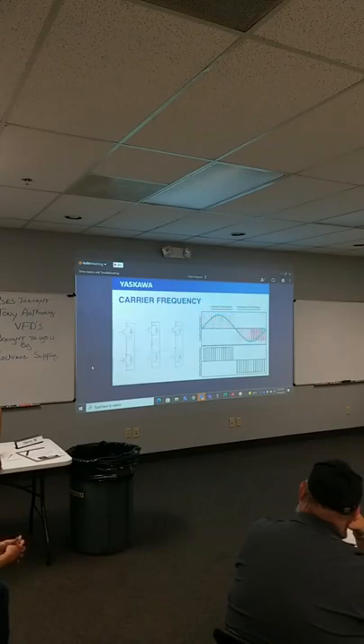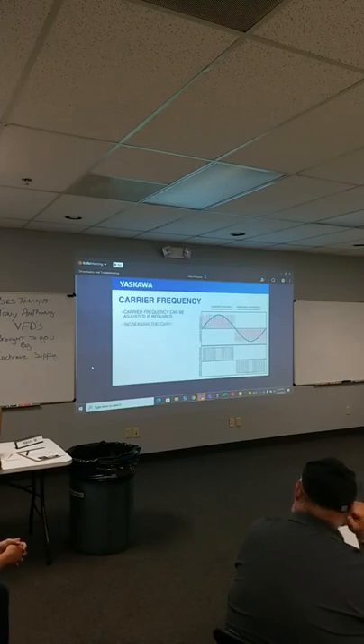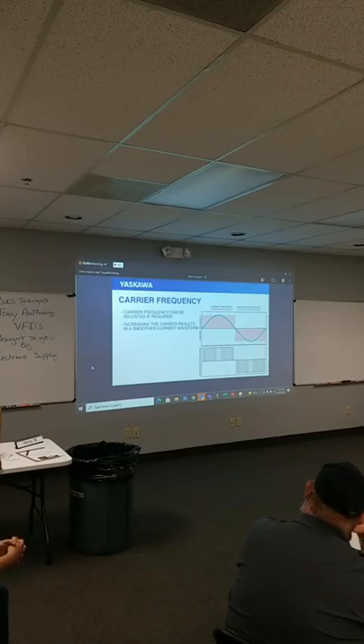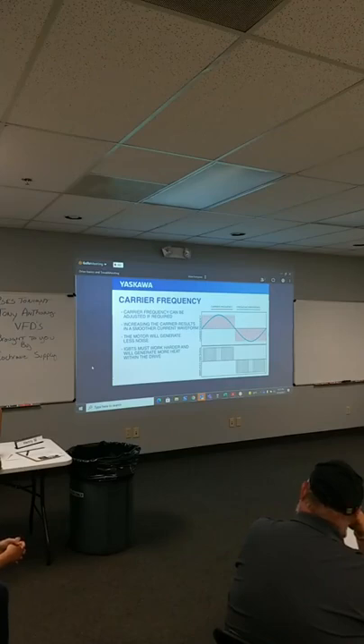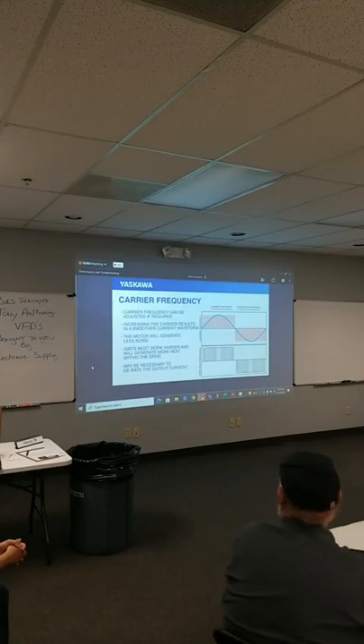Now, the rate at which IGBT switching occurs is known as the carrier frequency. This switching frequency can be adjusted if need be. Increasing the carrier will result in a cleaner, more sinusoidal current waveform, which in turn will make the motor generate less audible noise. However, this will also make the IGBTs work harder and create more heat in the drive. It may be necessary to derate the output current of the drive to accommodate the increased carrier frequency.